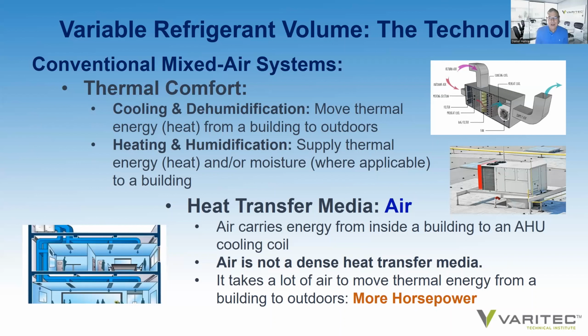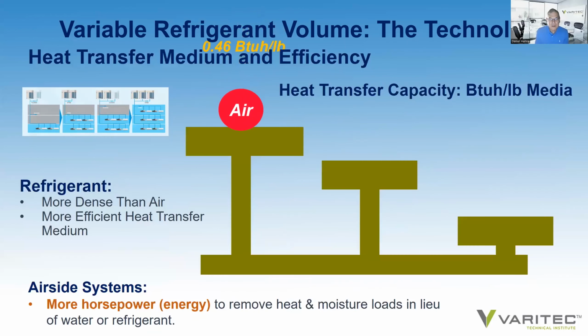The problem is that air is not a very dense heat transfer medium. It requires a lot of air to move the energy gained during the day, either sensible energy, which is the measure of energy in a space as read by a thermostat, or latent energy, which is the amount of energy necessary to hold water in a vapor or gaseous state. Air can only hold 0.46 BTUs of energy per pound of air. So you need a lot of air to move the energy gained in a space during cooling mode to deposit it effectively outside so you can maintain building conditions.